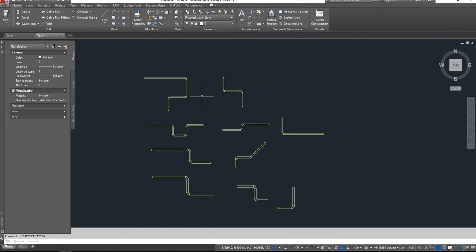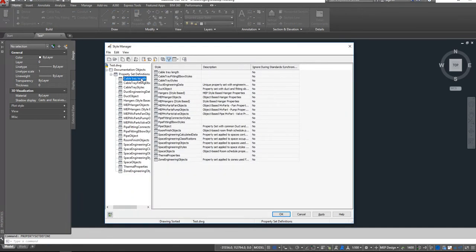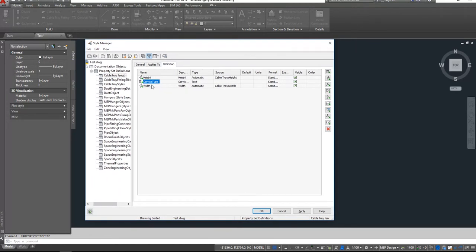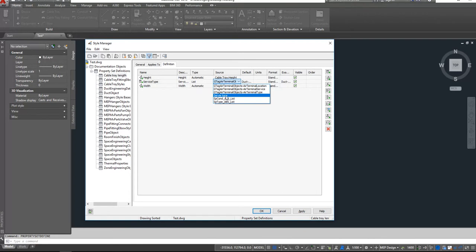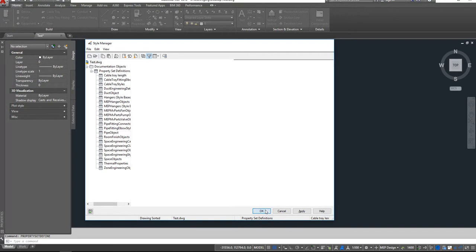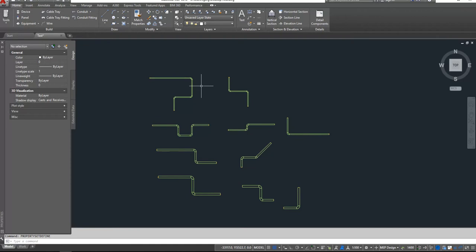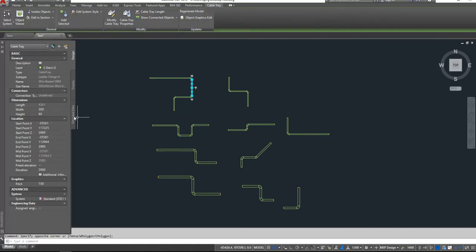So we have now created the property sets and the list of property definitions. And now we will go back to Property Set Define, go to our Cable Tray Length, and we will say that we want to add in our Service Type. We want to add type and list, and source will be Service Type. So now we have some drop-down menu of our service type cable trays.